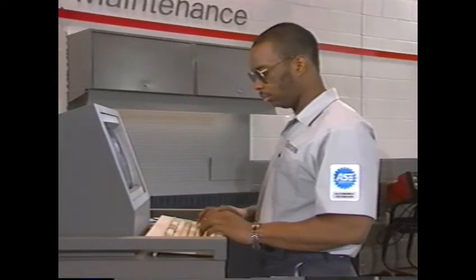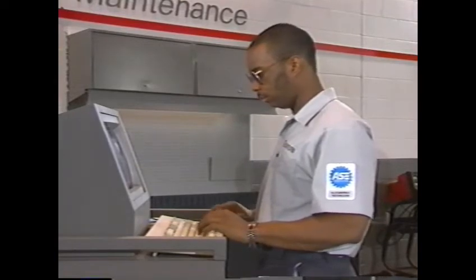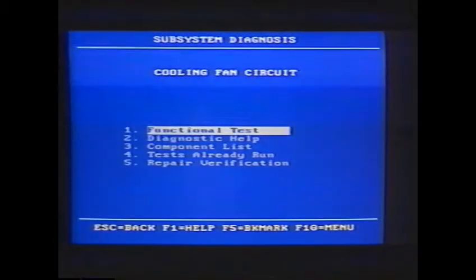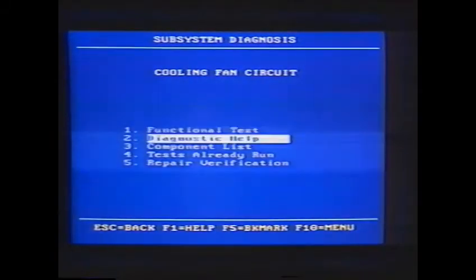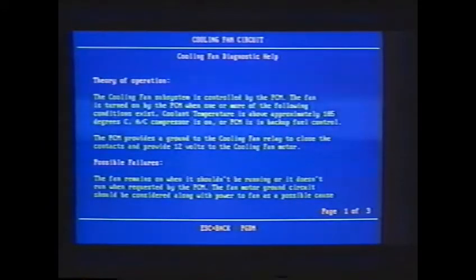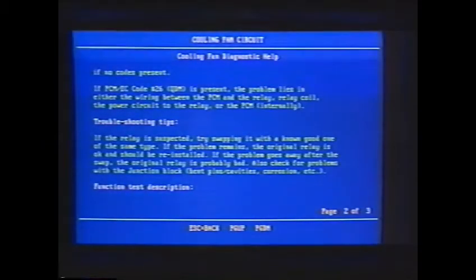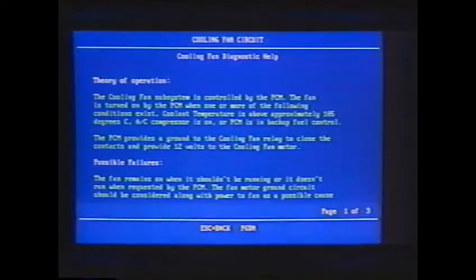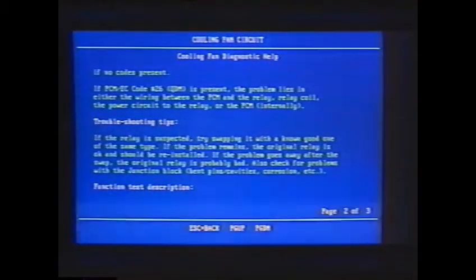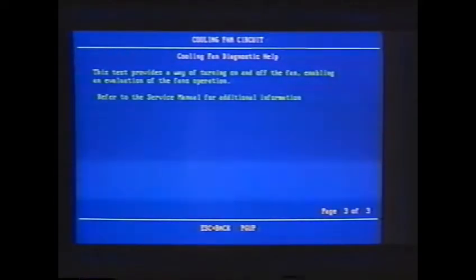Once a subsystem has been selected, in this case Subsystem 1 of Fault Group 1, you will see the Subsystem Diagnosis screen, which gives you 5 choices. In addition to Functional Test, you have Diagnostic Help. These screens give you information to help you isolate components within a subsystem that may be malfunctioning. It also gives you the theory of operation, normal measurements, troubleshooting tips, possible causes of failure, and functional test descriptions.